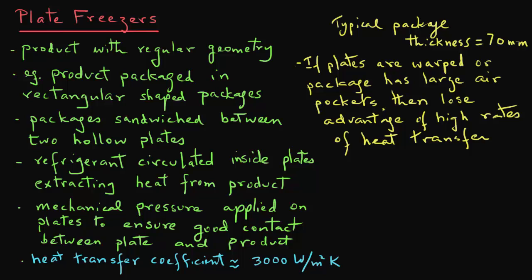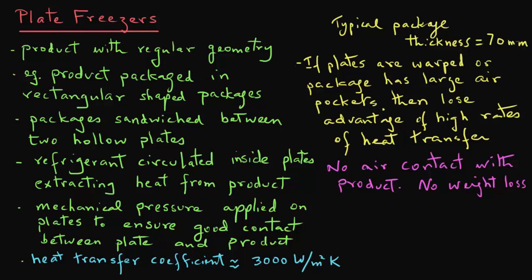This is because of either not a very good contact between the package and the plate, or considerable air space within the package. Note that in a plate freezer, since we are not using air, we really don't have any dehydration losses that one may get in other freezers where we use air as the cooling medium. So there is no weight loss of the product when it is frozen in a plate freezer.